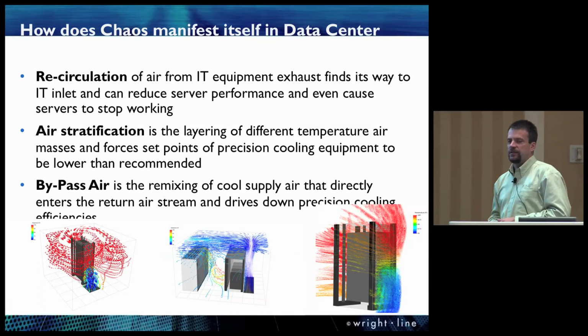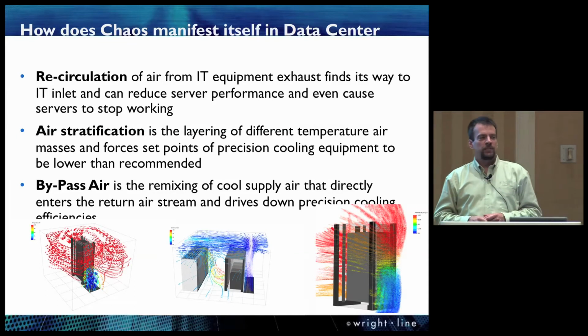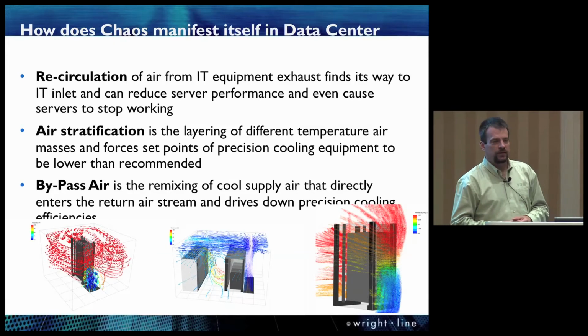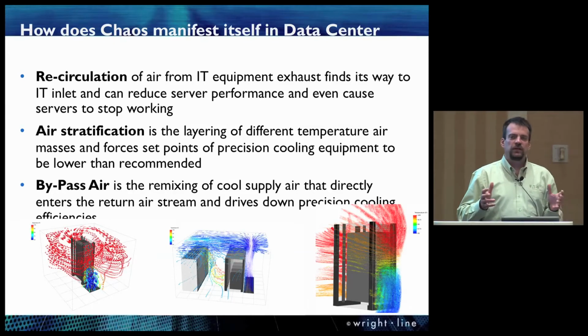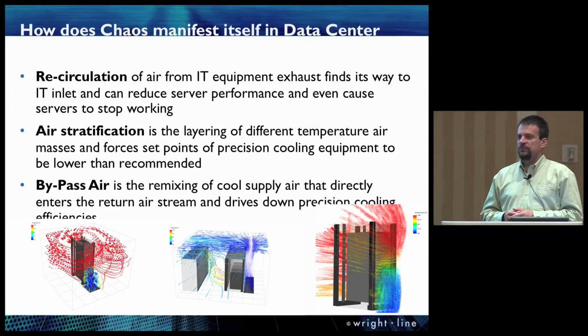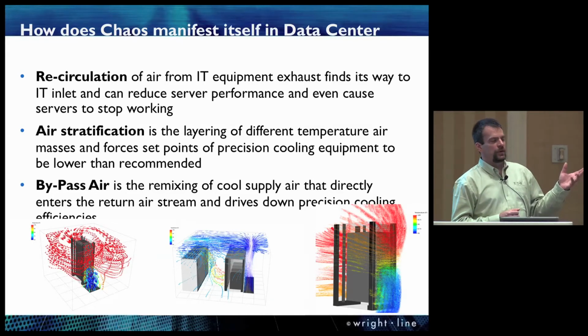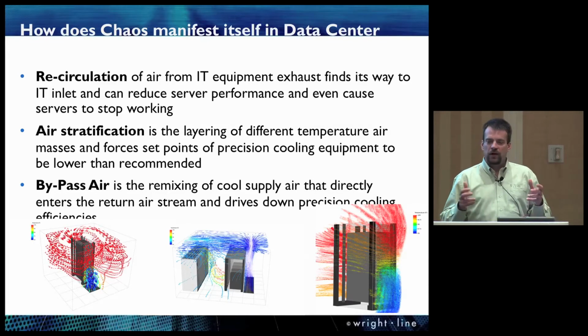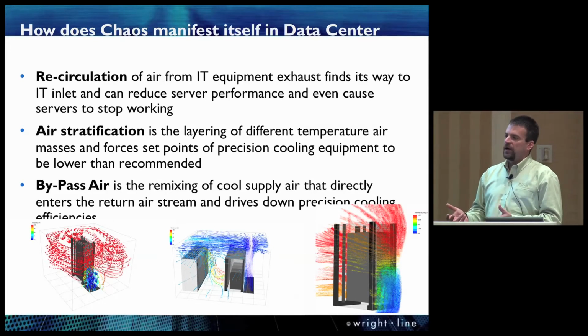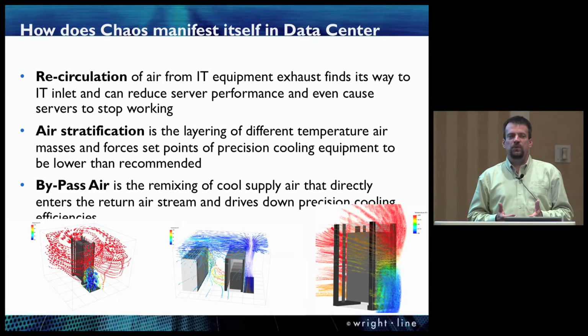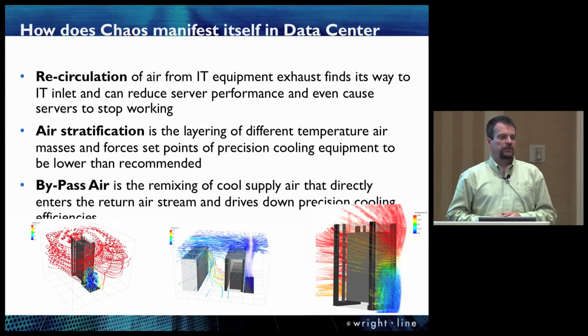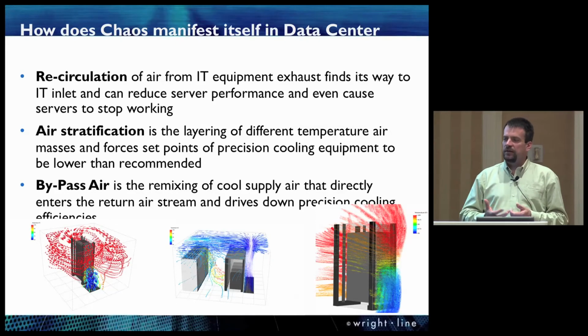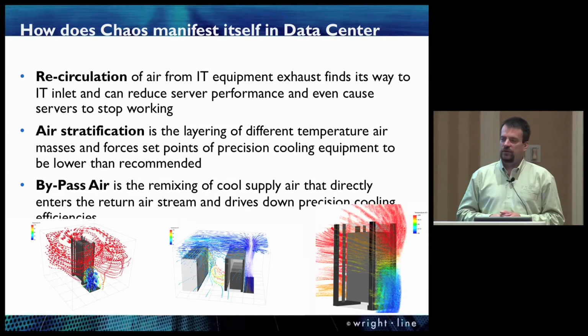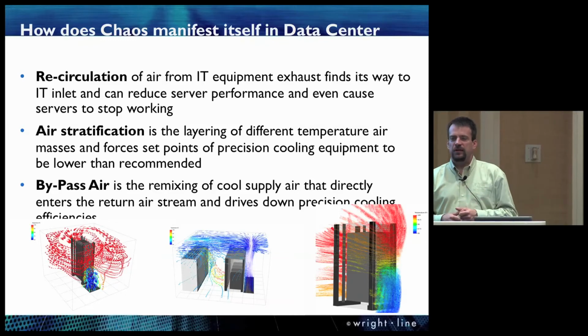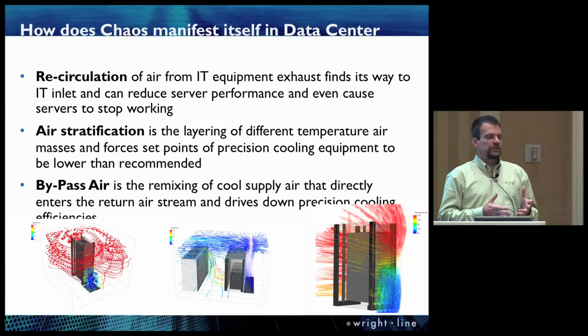Ideally, how does this manifest itself in the current data center today? If you've been in data centers, particularly legacy cooled data centers, you've seen these three typical problems. The first that we're talking about is recirculation. A lot of times warm air is making it back to the front of the IT equipment and is being pulled in as a supply air temperature. And obviously as that continues to feed on itself, it will eventually get too hot for the server equipment, and this creates hot spots.